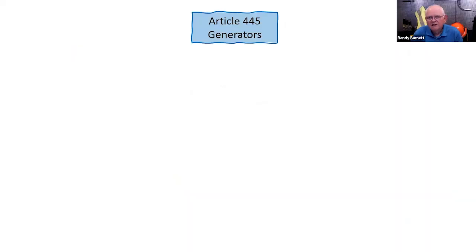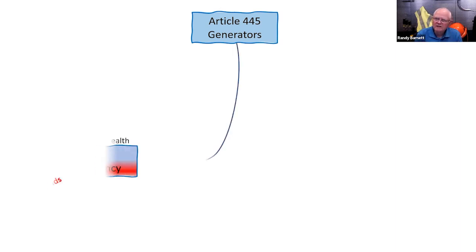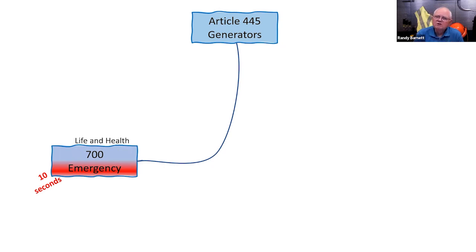We find our first information on generators in the NEC in Article 445, which covers general requirements for installation of generators. But we need to know about the applications as well. Back in Article 90, it talks about how Chapters 5, 6, and 7 supplement the information in those first four chapters. So we have Article 445 for installation requirements, but we also have an article in Chapter 7 — Article 700 — for emergency systems. If I'm installing a generator as an emergency system, these additional requirements apply.